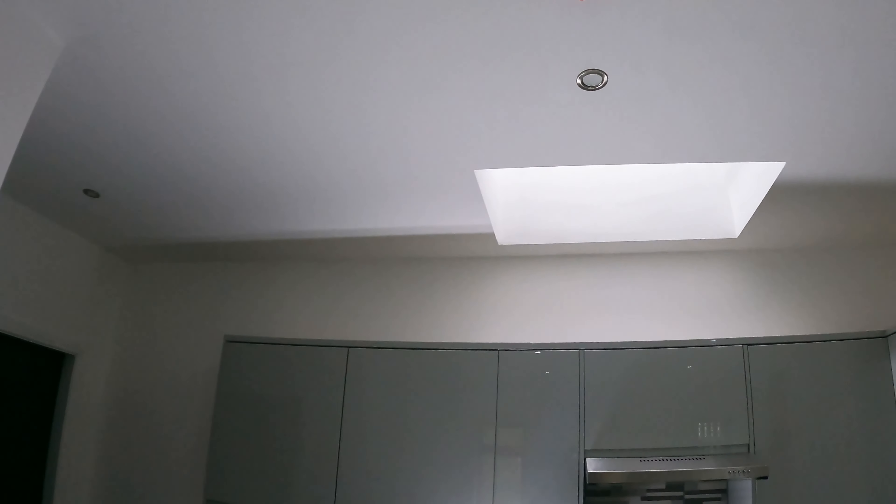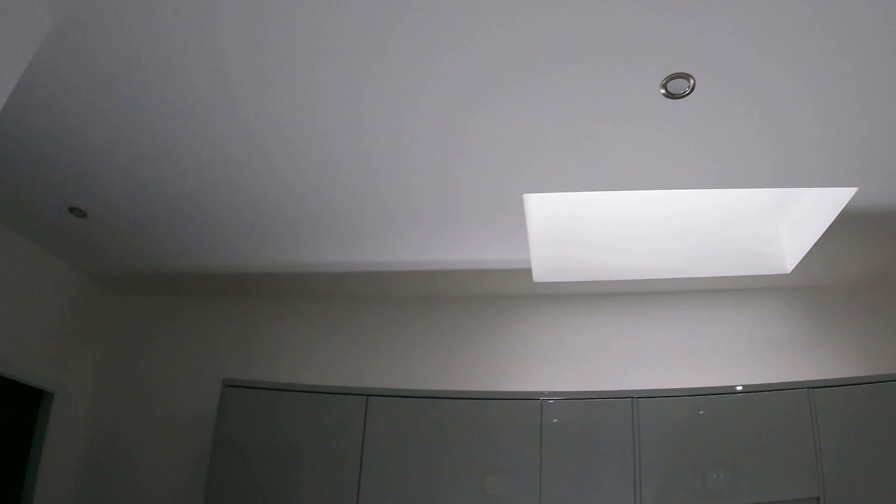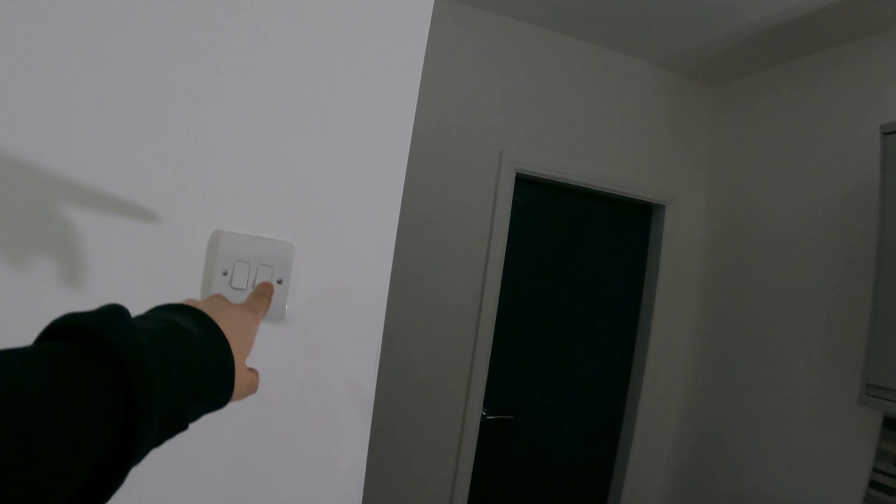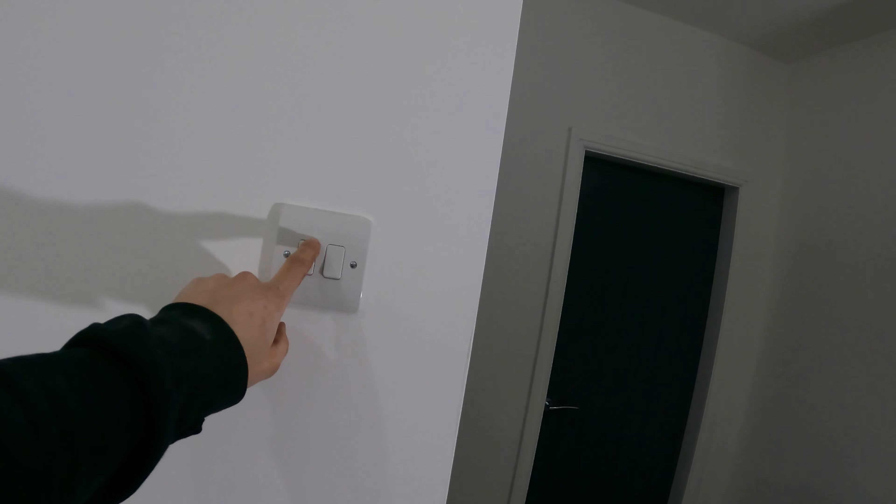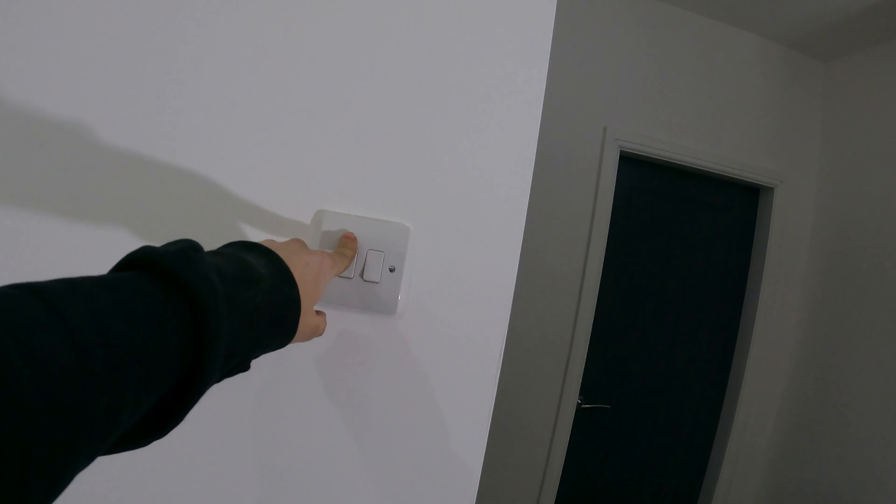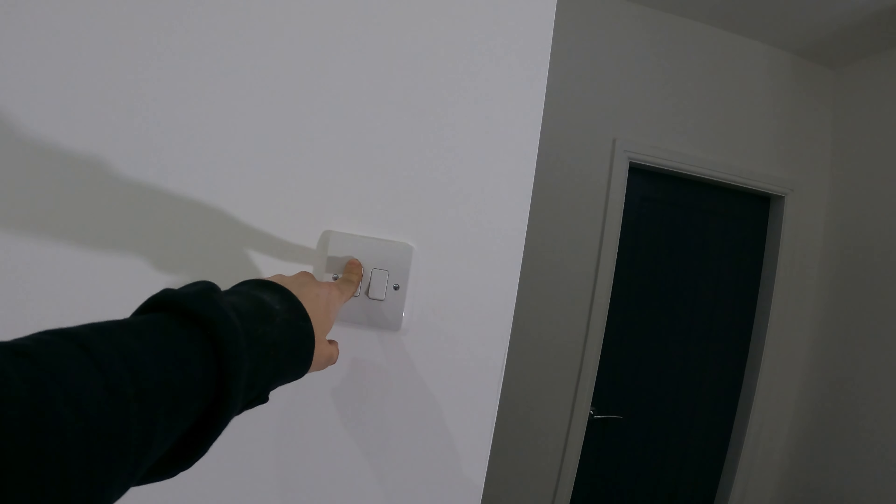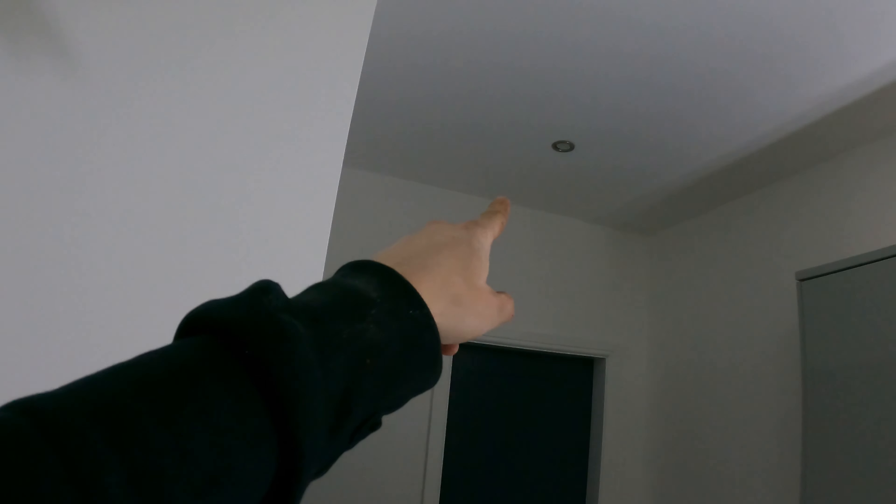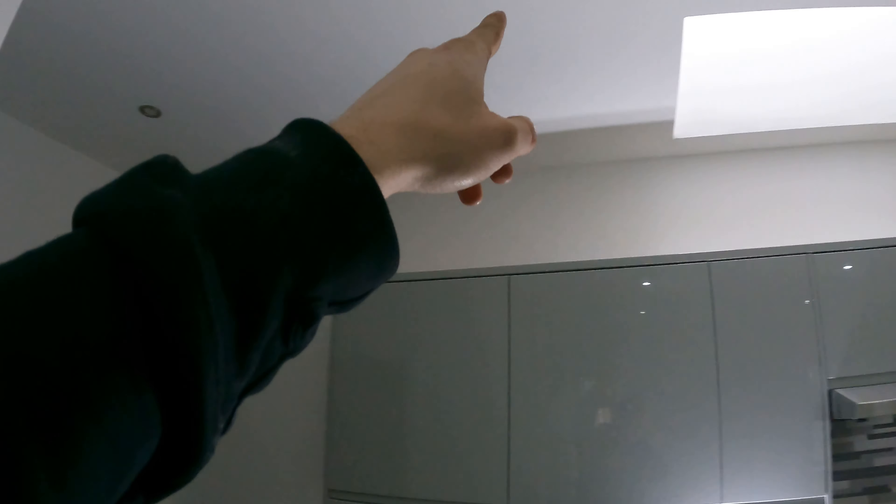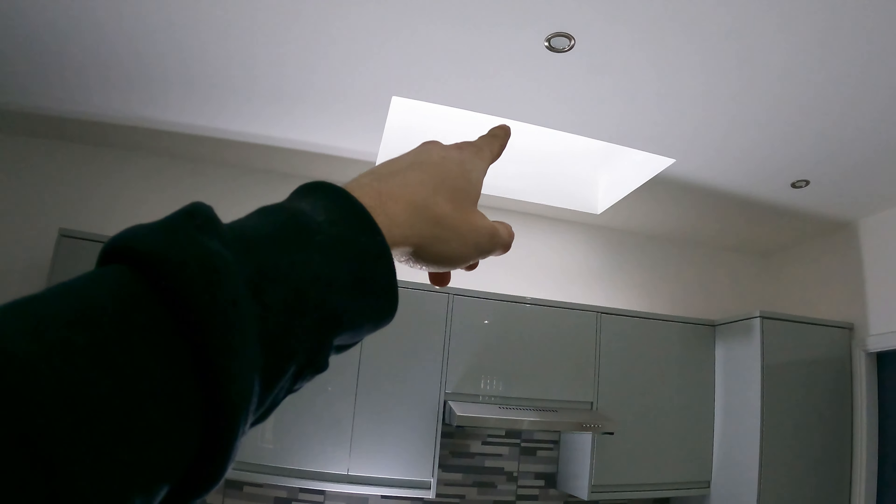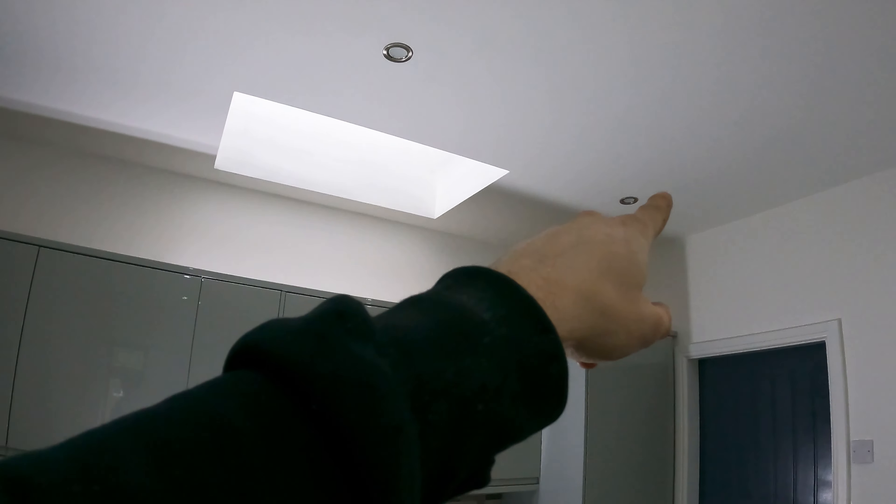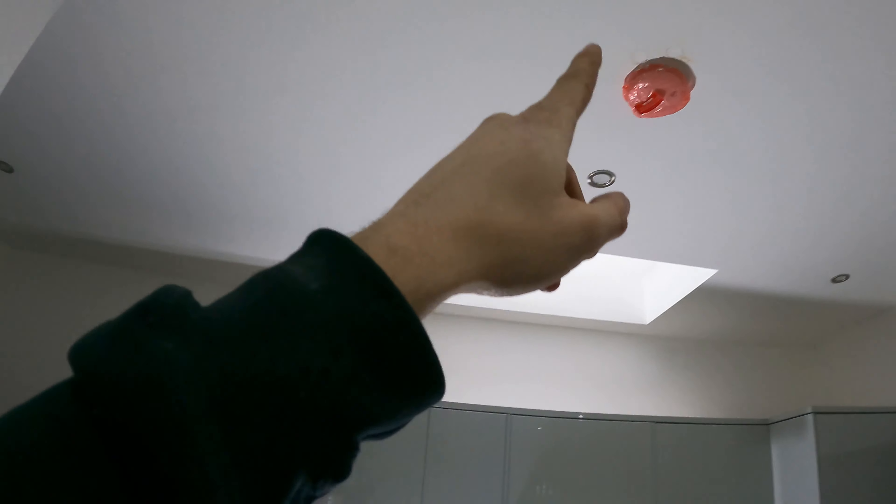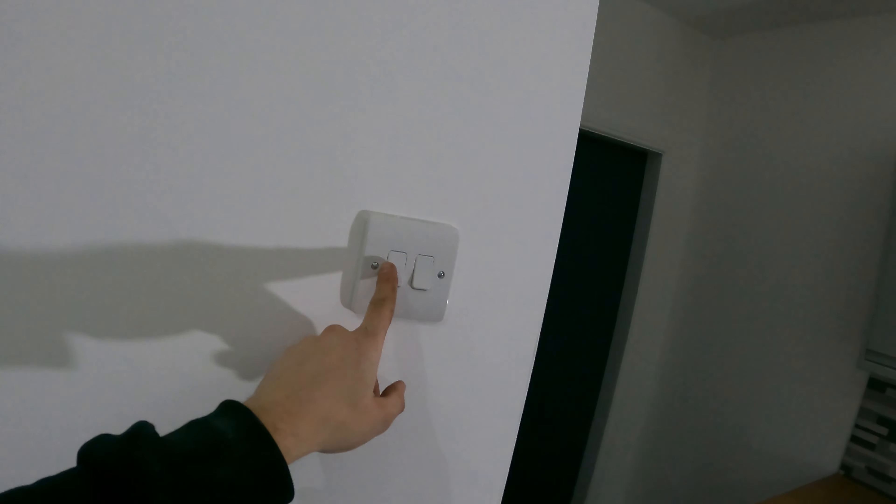I don't know if you've watched the previous video, but this builder, he'd wired a feed from the mains board to the switch, and from the switch he'd wired like a ring. So he'd gone up, gone to the first light, gone to the next light, gone to the next light, and in this case also gone to the smoke detector and come back down.